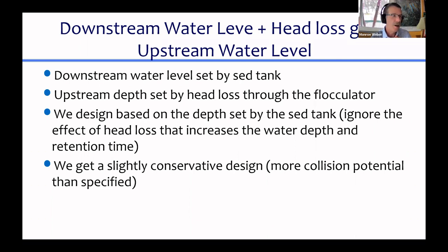You can't have a waterfall and expect flocs to survive. Once you've flocculated water, you have to treat it very, very carefully. And it only takes one little bad engineering design to break up all those flocs again. It wouldn't even require a waterfall. It could even just be a place where the velocity was extra high, where there was a little bit of head loss.